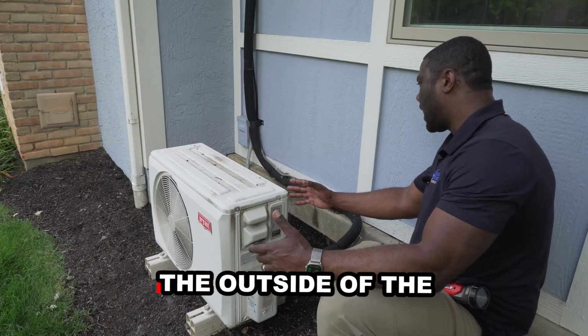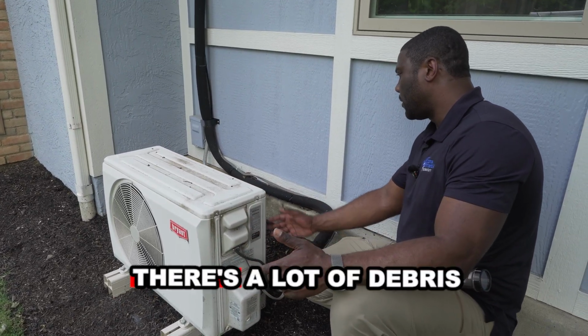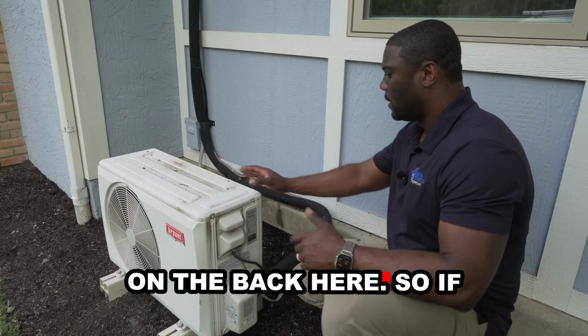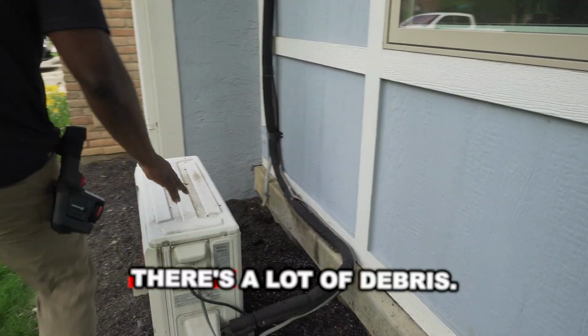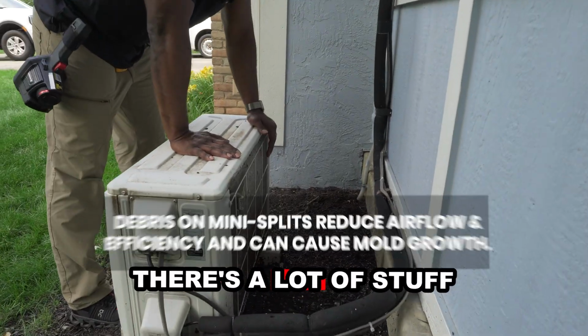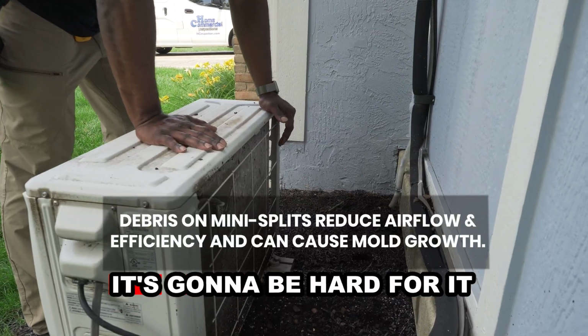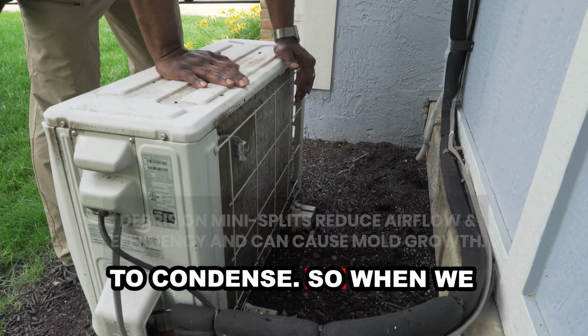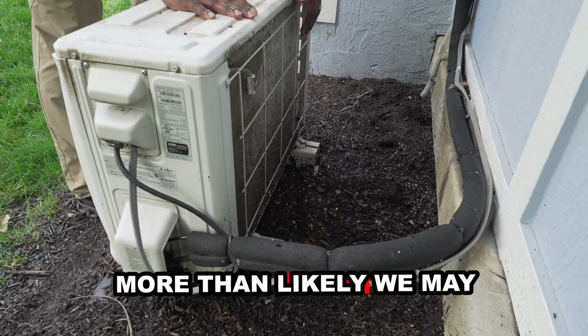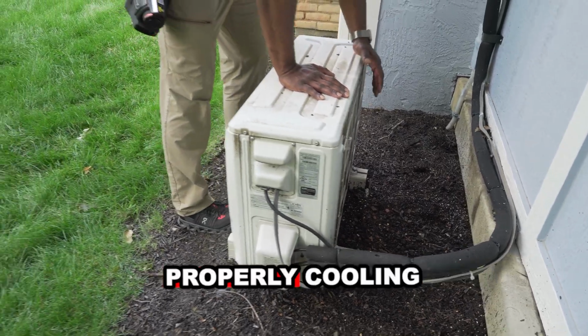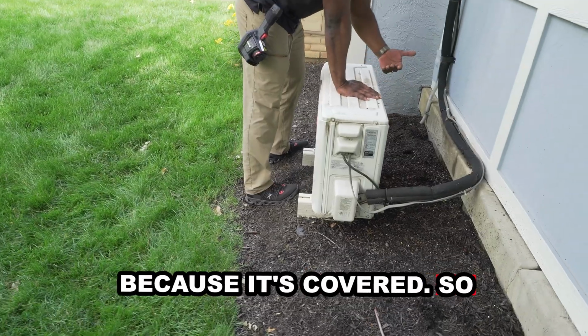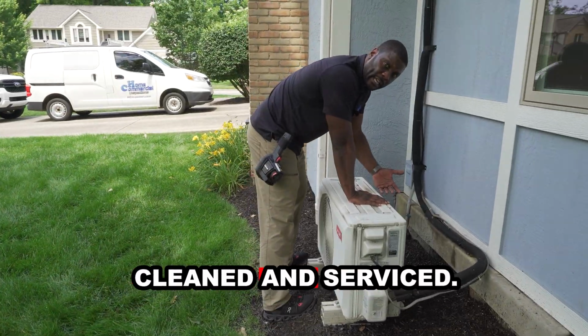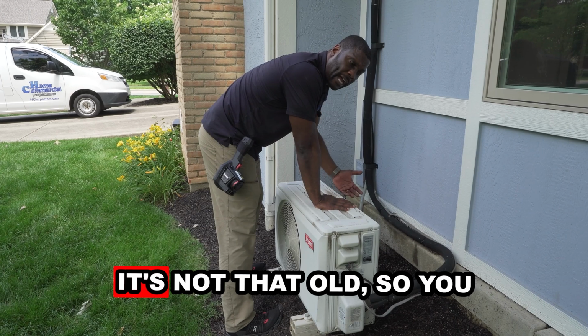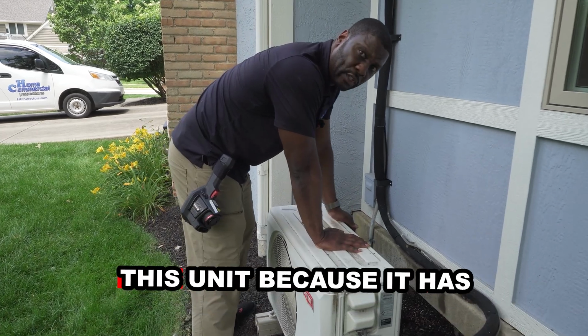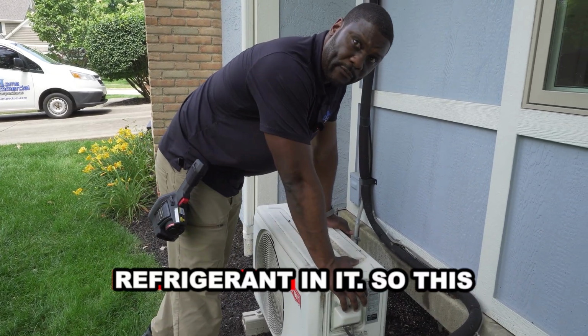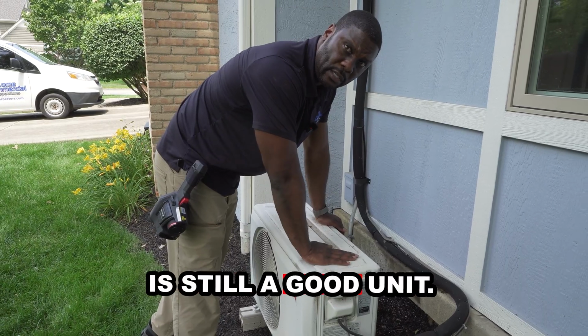So on the outside of the condensing coil, there's a lot of debris on the back here. So if you take a look here, there's a lot of debris. There's a lot of stuff covering the coil. So it's gonna be hard for it to condense. So when we go inside, more than likely we may have some issues with it properly cooling because it's covered. So this really needs to be cleaned and serviced, okay? It's not that old, so you could probably service this unit because it has R410A refrigerant in it. So this is still a good unit, okay?